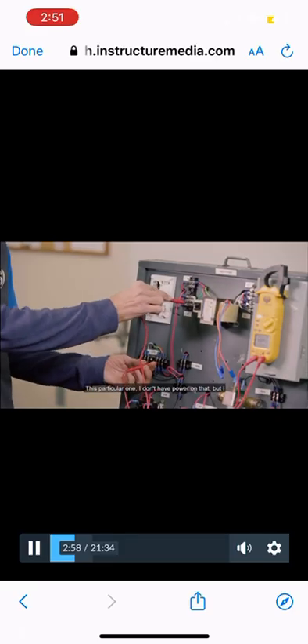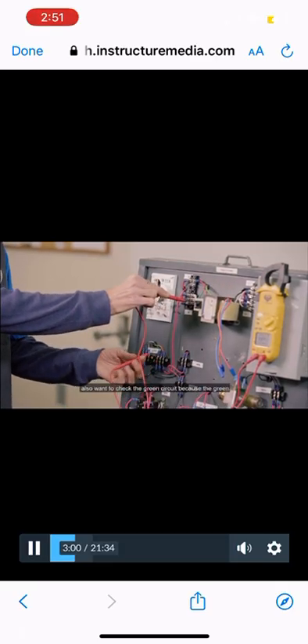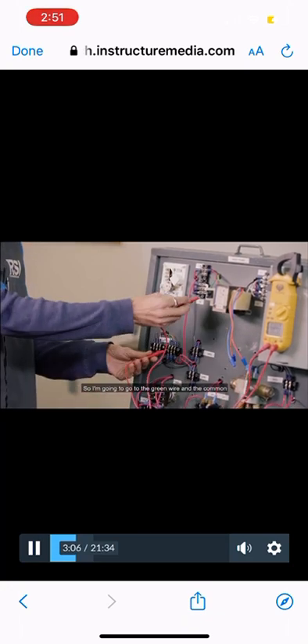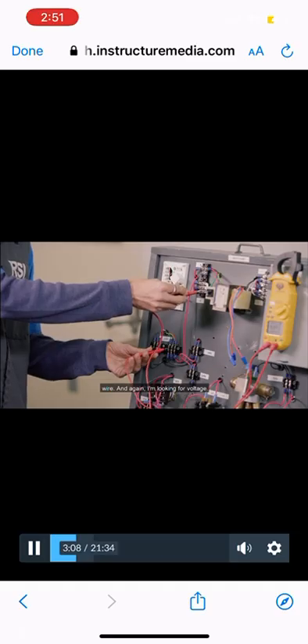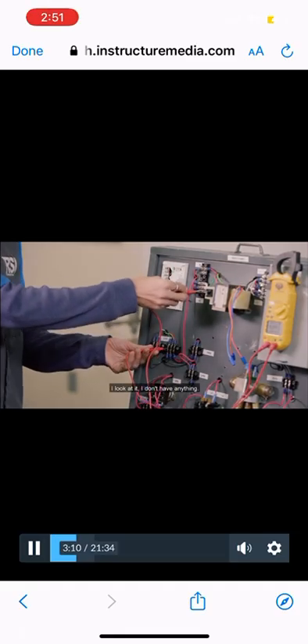And I'm looking for voltage again. That means the thermostat is sending it back out. This particular one, I don't have power on that. But I also want to check the green circuit, because the green circuit is what turns my blower on here. So I'm going to go to the green wire and the common wire. And again, I'm looking for voltage. I look at it, I don't have anything.